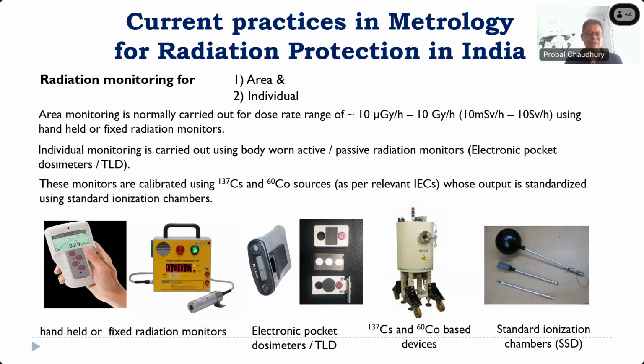Individual monitoring is carried out by the TLD, thermoluminescence dosimeter, as I have mentioned, or by pocket dosimeters worn by the person, which record the radiation. These monitors are calibrated using the cesium and cobalt sources as per the IEC standards, and their output is standardized using the ionization chambers. These are some of the equipment shown: fixed radiation monitors as well as handheld ones, then electronic pocket dosimeters, and then standard ionization chambers.